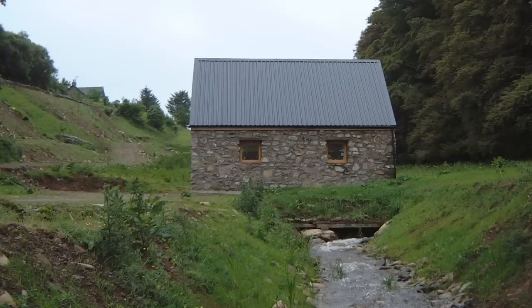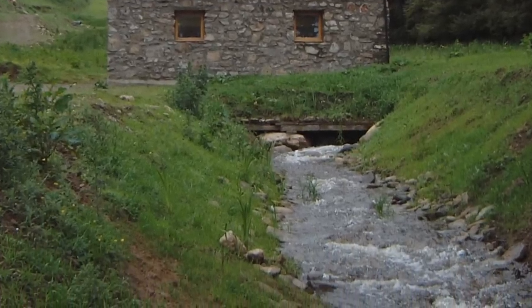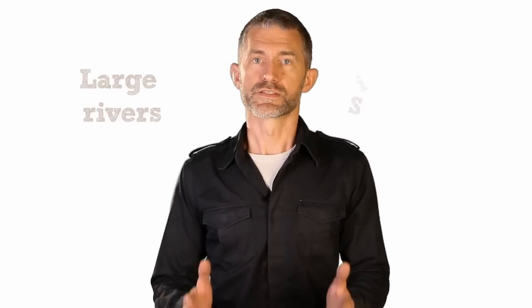The head of a river can be natural — for example, a stream flowing downhill — or it can be artificially generated by building a weir or dam. While there are systems that operate mainly on flow, they require a very large river with a very high flow rate, and large volumes of water need to be extracted. Sites like this are unlikely to be suitable for community-scale projects. Large rivers with significant falls are the best sites for hydro, because they have high head and high flow. Rivers with low head and low flow are no use at all. Rivers with high head but low flow can be a decent bet, but only as long as they actually flow most of the time — some small fast-flowing rivers dry up during the summer.